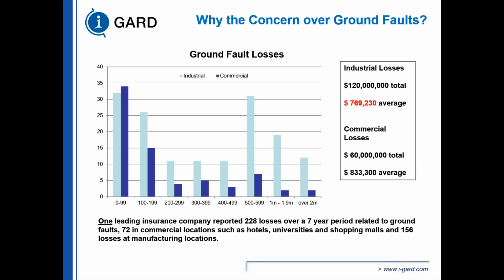So $120 million came from industrial facilities. On average, $769,000 in losses average per 156 claims. For commercial losses, $60 million, average $833,000. And you can see that a lot of the claims, particularly industrial, are well over $500,000 to over $2 million. So it's very, very costly to have losses from what is commonly referred to as the most typical kind of fault that you can have in an industrial facility or a commercial facility. And you can prevent all that with some minor changes to your grounding system.